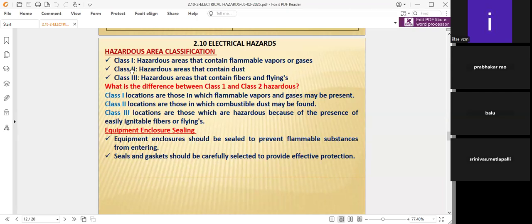Class 2 is a hazardous area that contains dust. Where hazardous dust is there, very, very important. So what do you consider dust to mean? Dust means process dust, or we can say atmospheric dust. Suppose a wooden chipping area is there, or lime kiln areas, or lime dust areas. Where a dust-prone area is there, we have to take care of dust explosion and see that the dust extraction system is proper. That is what is meant by dust.